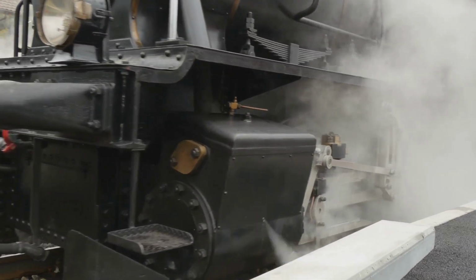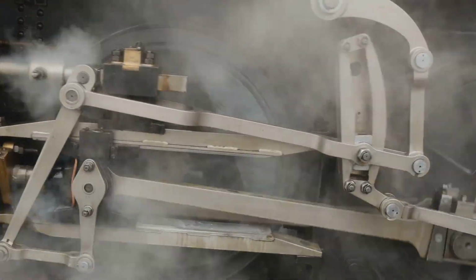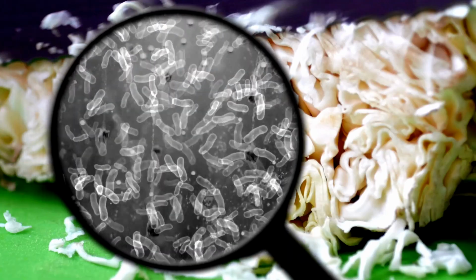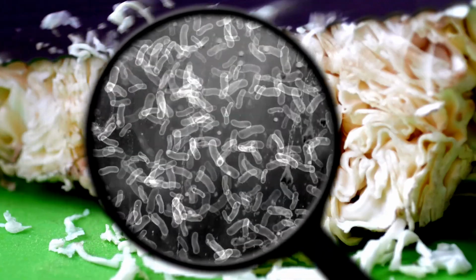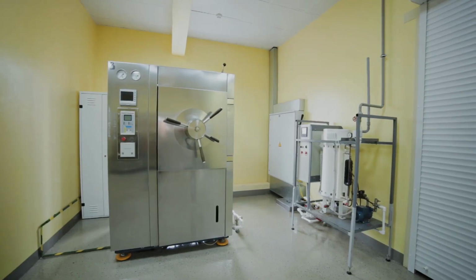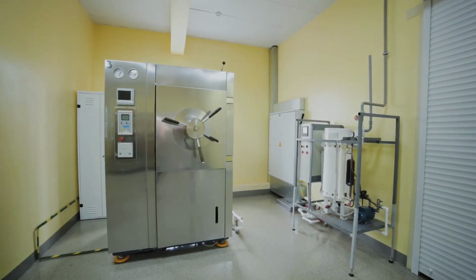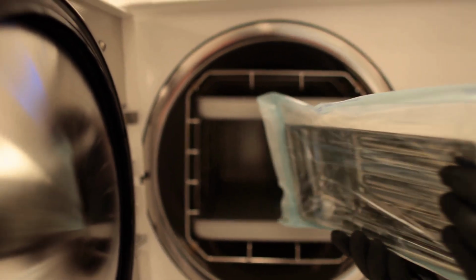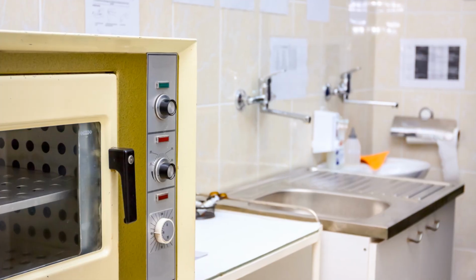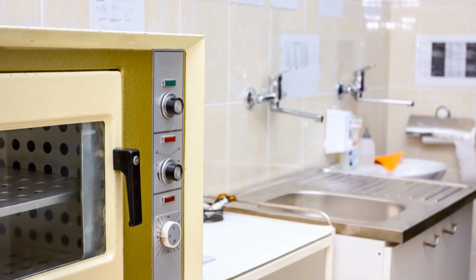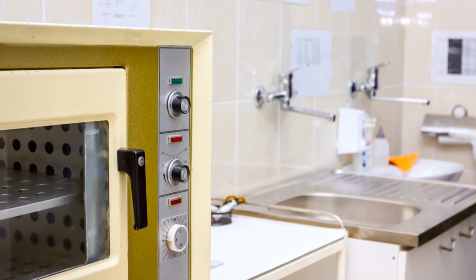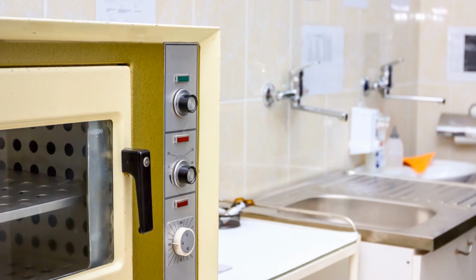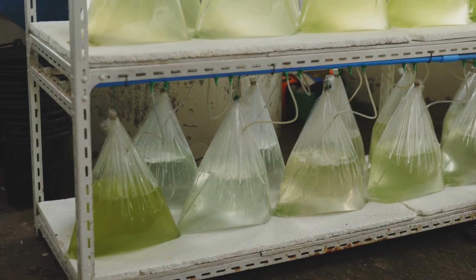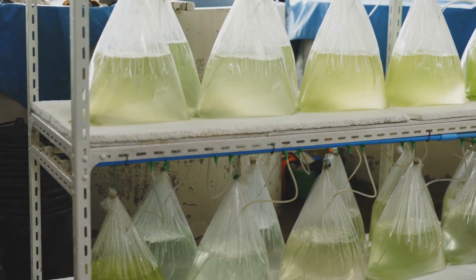One of the oldest ways to kill germs is heat. Heat destroys essential proteins and enzymes. Cells fall apart. The most common professional form is pressurized steam. An autoclave looks like a high-tech pressure cooker. Pressure lets steam reach higher temperatures. 121 degrees Celsius for 15 to 30 minutes is typical. That heat plus moisture combo kills even tough bacterial spores.